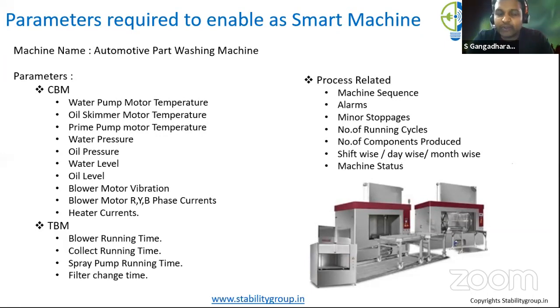You can find out whether shaft misalignment is happening, whether there's a bearing problem, or a winding problem. All these things can be found using vibration data - three-axis vibration data, X, Y, Z axis.